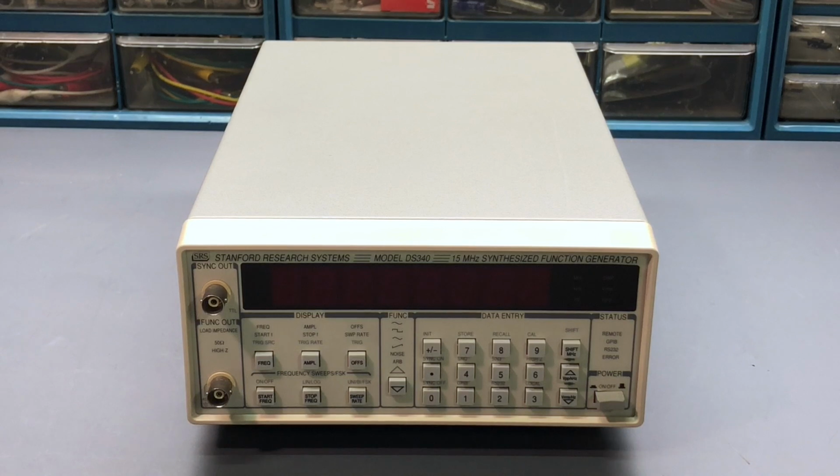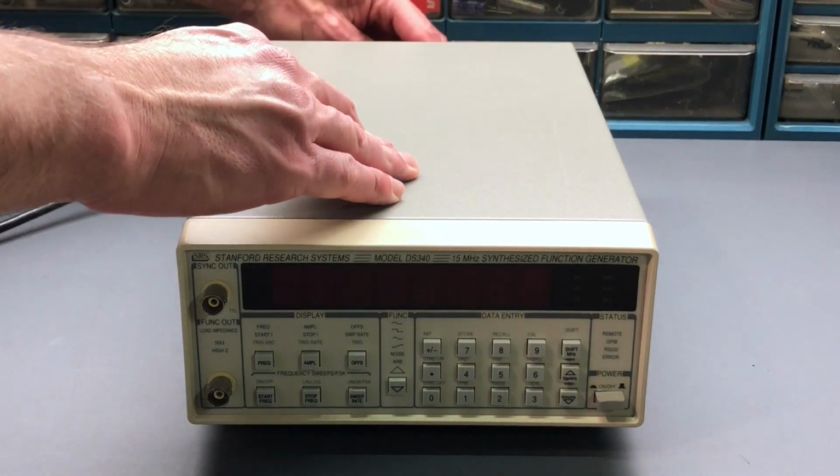So let me power up the instrument and take a look and see exactly what the fault code is, and then I will connect the output to my oscilloscope and frequency counter. Let's see how it actually looks without doing anything else, and just see what the outputs are. How the calibration looks, is the amplitude matching the displayed value, is the frequency matching, and so on. Just kind of get a feel for exactly what the issue is. Again, this instrument was reported to have something wrong with the calibration, so we want to take a look. That means something must be inaccurate on the output versus what it displays. So I will go ahead and power it up, and then we'll start on that troubleshooting. So I'll reach around here with my power cord and get this connected.